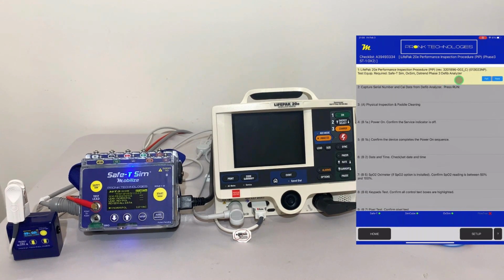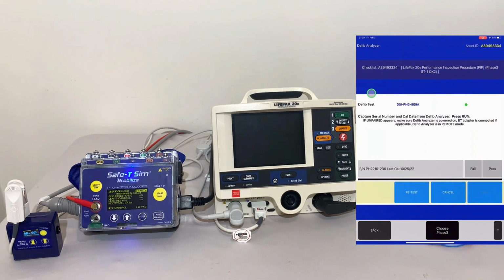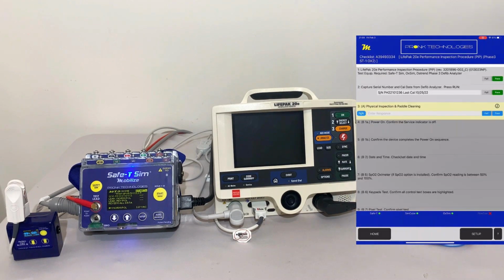As a technician, we're going to follow this step by step. I'm going to say yes, I reviewed that step and it's correct. Now we're going to do some basic things here. We need to capture serial number information and calibration date from our defib analyzer. To communicate with our defib analyzer, I simply tap the run button. It will request the information we need, which is the serial number and its calibration date. That information is good. We've passed that test, and we go on to the next step.